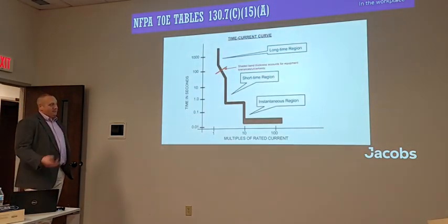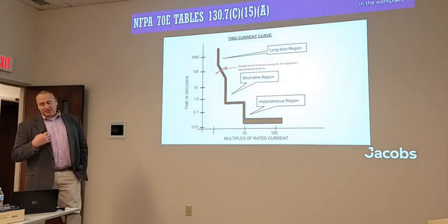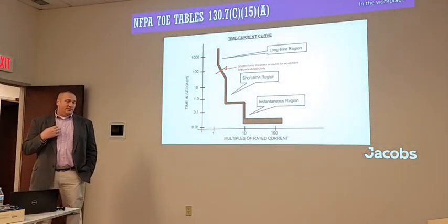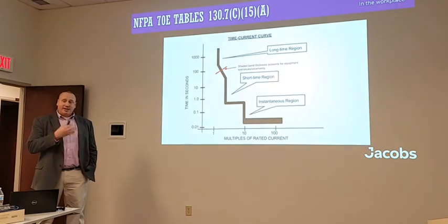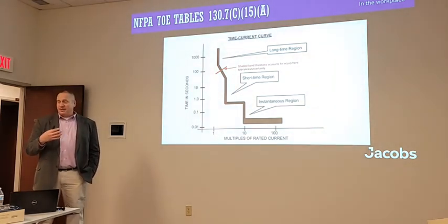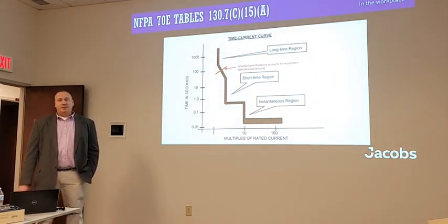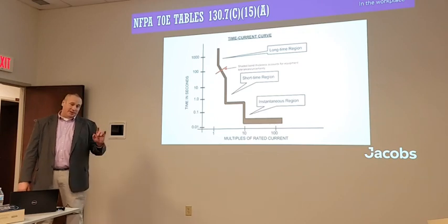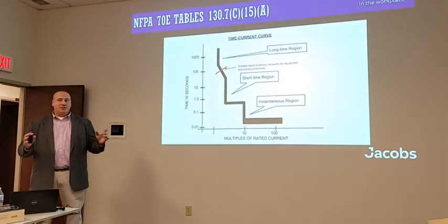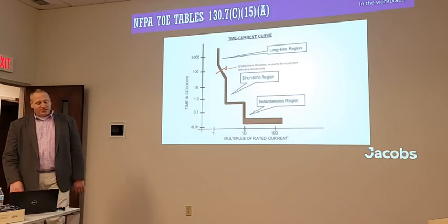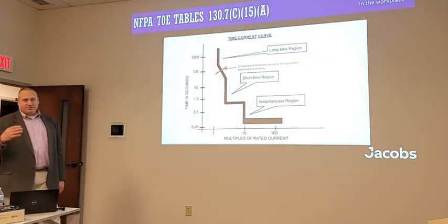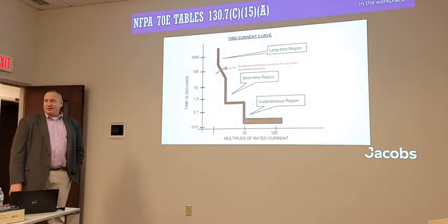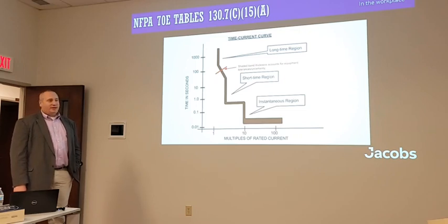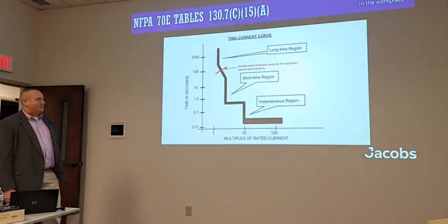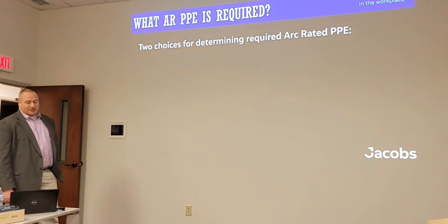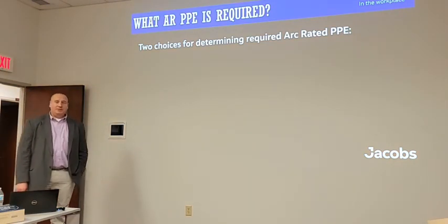So my approach, because I really like myself more than I think anybody else in the world, so if it's not stickered and the analysis hasn't been done, I'm going to be in a 40 cal suit protecting myself. Well, first I'm going to try to do it where I don't have to have the suit on, figure out a workaround. If I absolutely have to put a suit on, then I'm always going to wear the 40 cal and be dressed out as much as I possibly can so that I have the highest probability of going back home. I'd rather sweat for a little while than risk waking up in a burn center, because that would be really bad.